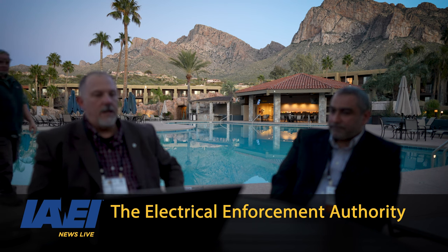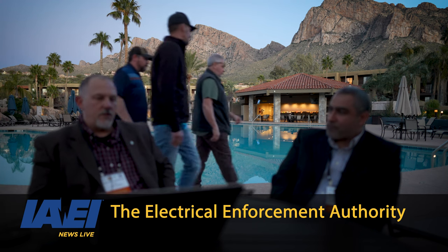But the challenge is, not always will it increase incident energy, but there's a good chance you will, especially if you bring a breaker solution to the table. You're adding intentional delay, and we know incident energy is current and time. So if the ground fault current is the same and you're delaying your trip time, then you're adding energy. That's just simple math.